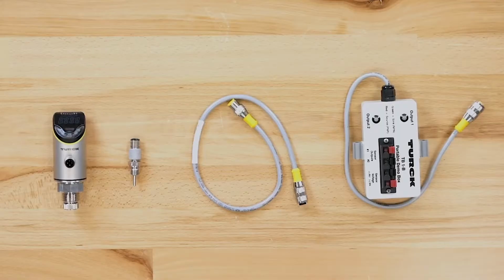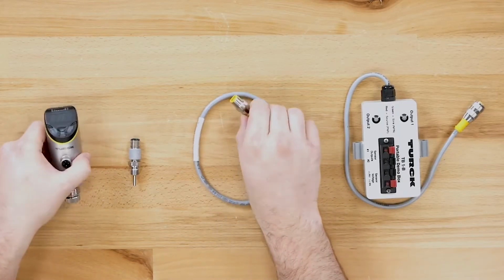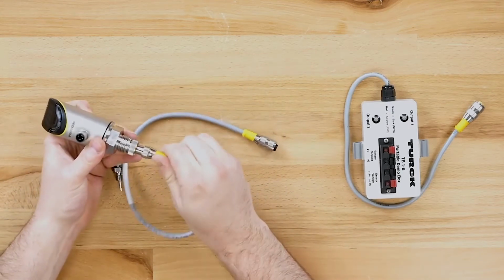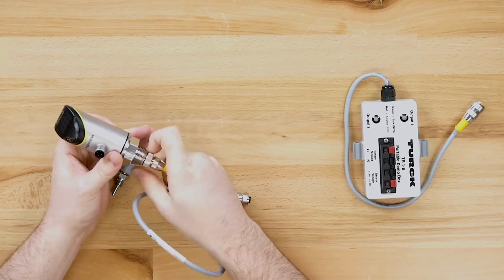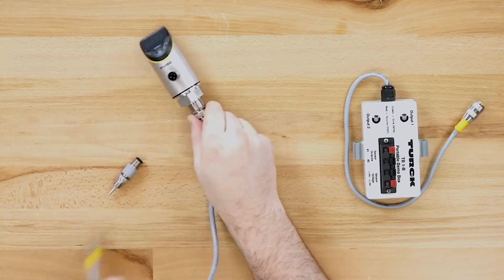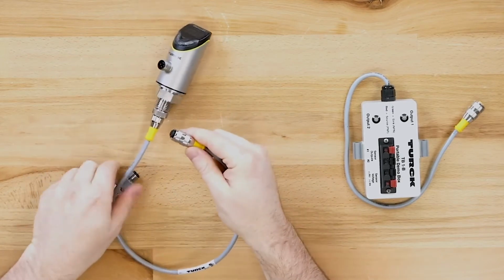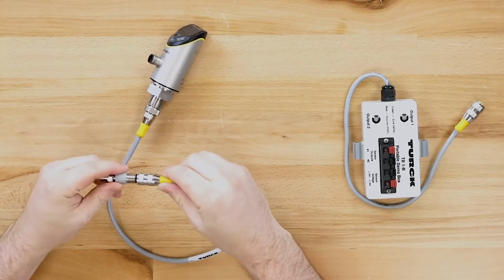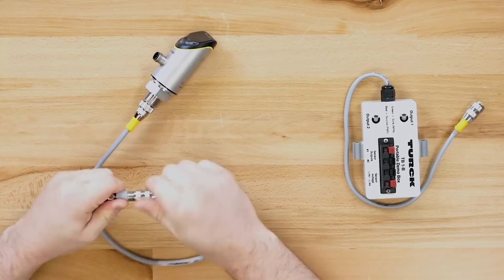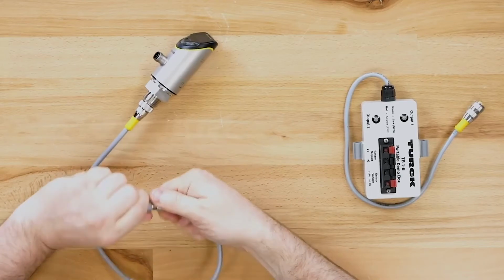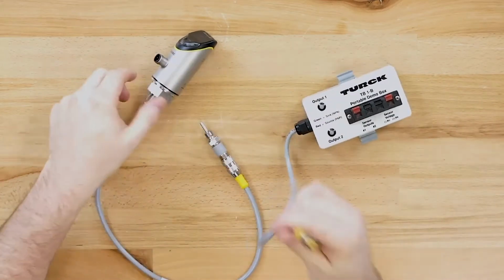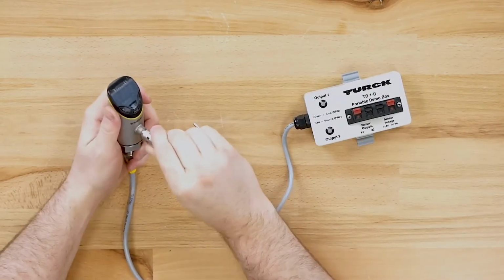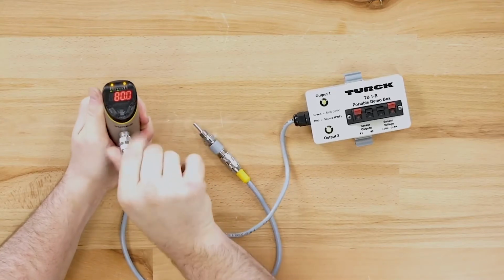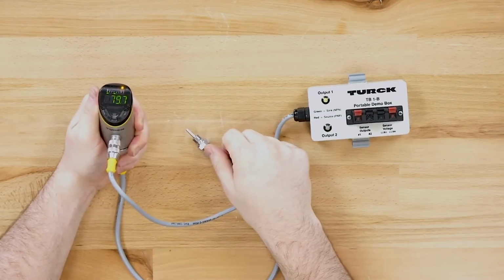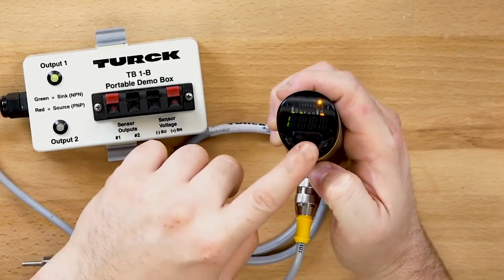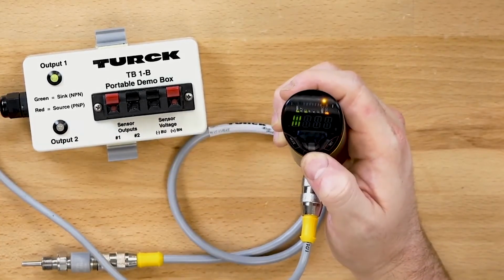First, let's put together the hardware. With an M12 cordset, plug the male end into the bottom of the TS Plus sensor. The female end of that same cordset, install it onto the male end of the temperature sensor. And then finally, we'll apply power to the TS Plus sensor with the Turck test box. To unlock, press the Enter touchpad for 4 seconds and then swipe all touchpads from left to right.